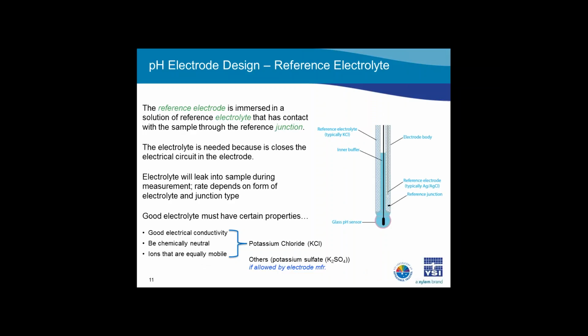At this point, I did want to further clarify the interaction between the reference electrode, reference electrolyte, and the junction. The reference electrode is placed in a solution of reference electrolyte that has contact with the sample through the reference junction. Therefore, the electrolyte has a connection to the sample through the junction, as it serves to close the electrical circuit in the electrode.